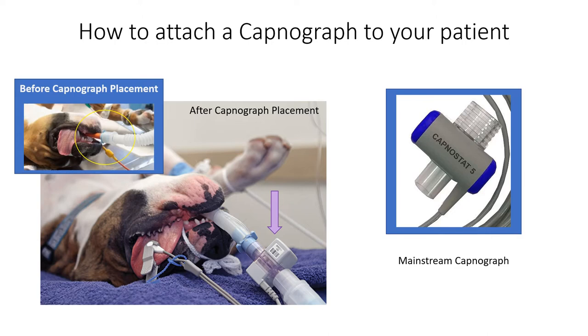The clear part that you see in this mainstream capnograph is a wearable item. In other words, it's meant to be replaced on a regular basis. If your readings begin to become wonky or there are cracks in it, it's definitely time to replace it. There are different colored pieces meant for different size patients. Usually you're going to see an adult and a pediatric size.